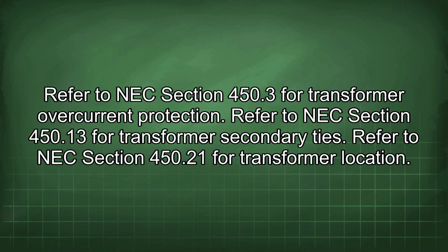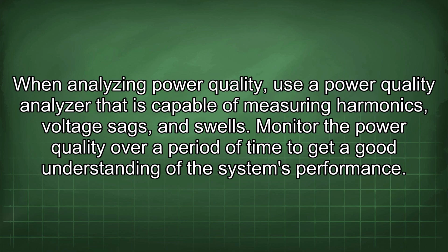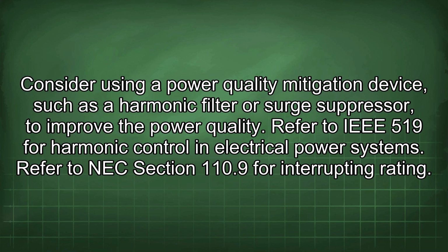Refer to NEC section 450.3 for transformer overcurrent protection. Refer to NEC section 450.13 for transformer secondary ties. Refer to NEC section 450.21 for transformer location. When analyzing power quality, use a power quality analyzer that is capable of measuring harmonics, voltage sags, and swells. Monitor the power quality over a period of time to get a good understanding of the system's performance. Consider using a power quality mitigation device, such as a harmonic filter or surge suppressor, to improve the power quality. Refer to IEEE 519 for harmonic control in electrical power systems.